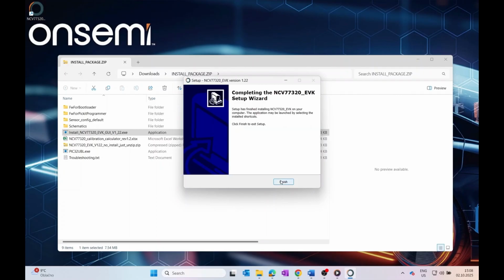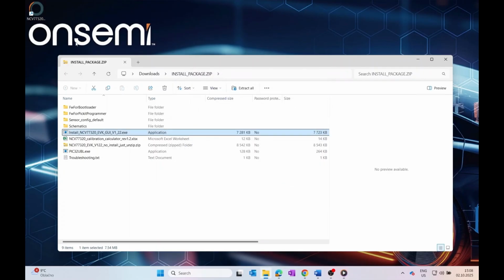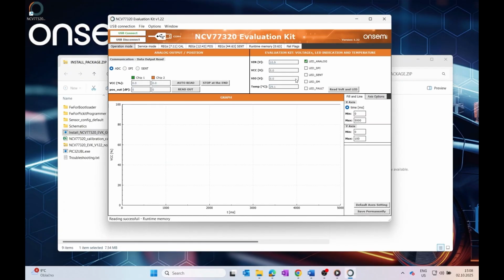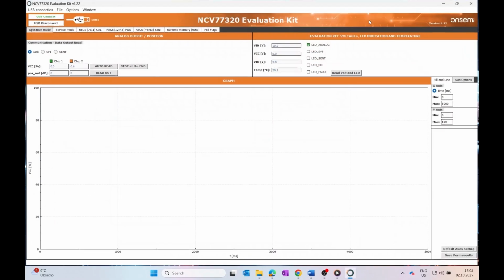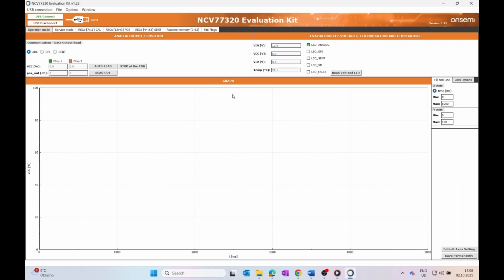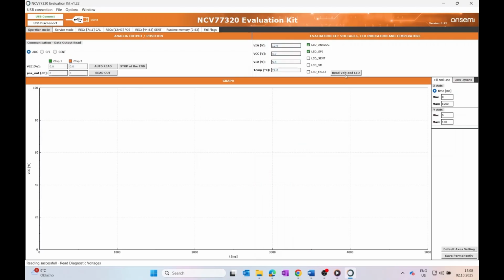run the application directly. Next, plug in the power adapter to the evaluation kit and connect the USB cable to your computer. Launch the application. If everything is connected properly, you'll see a green USB connected message along with the COM port number. If the kit doesn't connect automatically, switch to manual connection. List the available COM ports and select the correct one. Once connected, you can read diagnostic voltages and temperature from the board. Use readout for a single read or auto read for continuous monitoring. The position data will be plotted in the chart below.